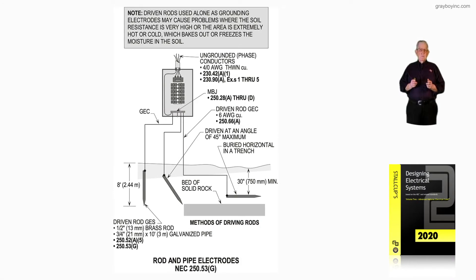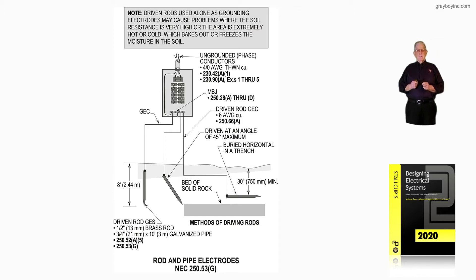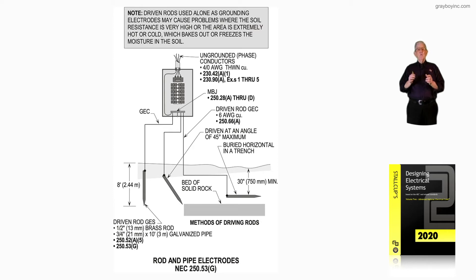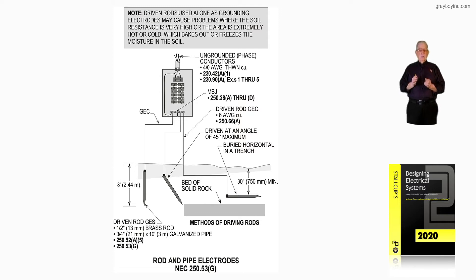This illustration deals with auxiliary grounding electrodes. Let's focus on the motor that is located outside of the building. Notice there's a driven rod driven out there for equal potential plane and also to divert surges that may come down the line. To size this auxiliary grounding electrode, we would review 250.54 of the code.